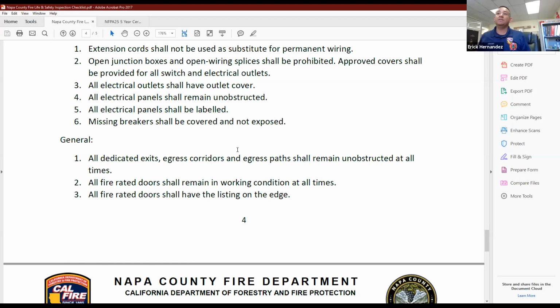That's a big one, and the reason for that is we know that a lot of businesses have very small space for storage, and sometimes I'm finding that it's very difficult for us to get into those electrical rooms, or even fire pump rooms, or we're finding that we have tons of boxes right in front of the riser for the sprinkler system. So make sure that you're providing a clear separation.